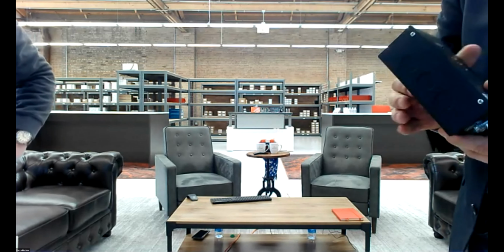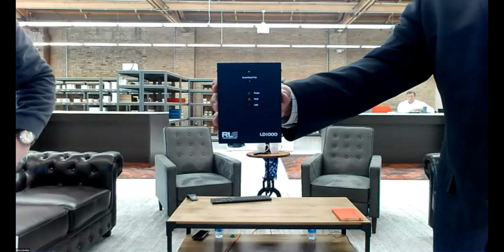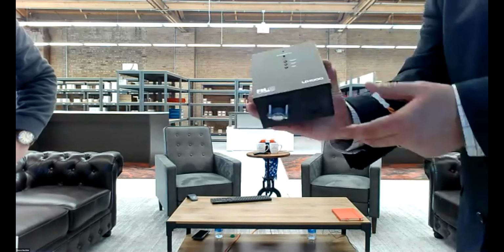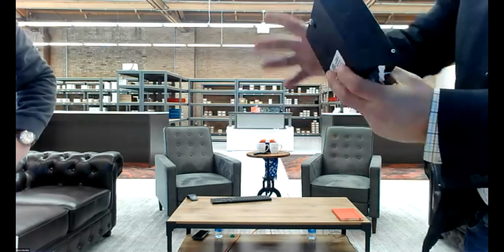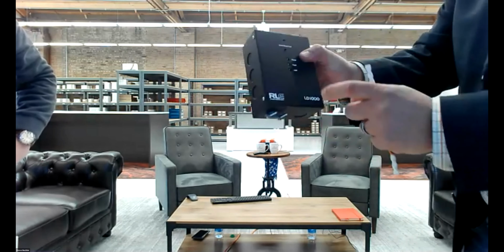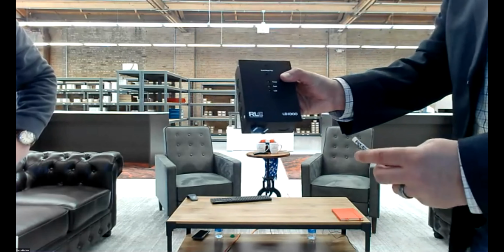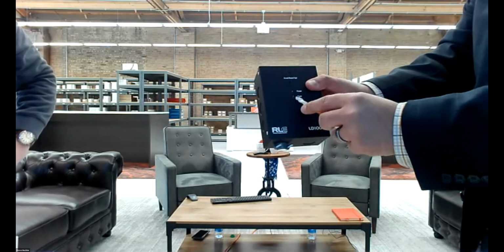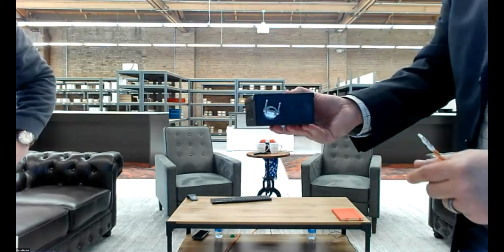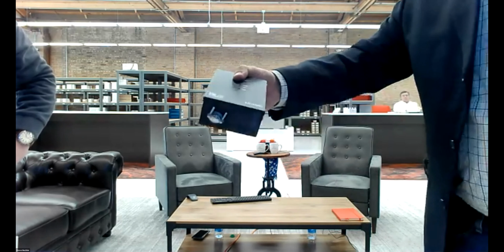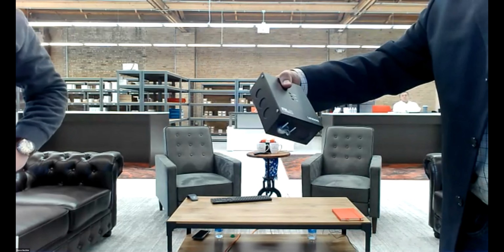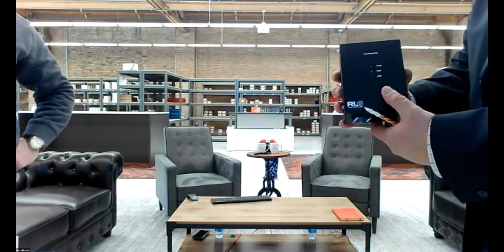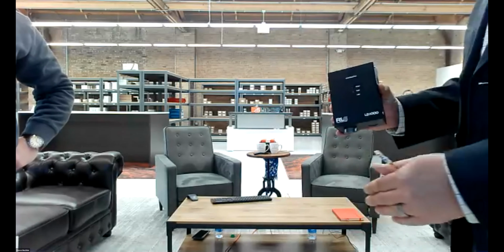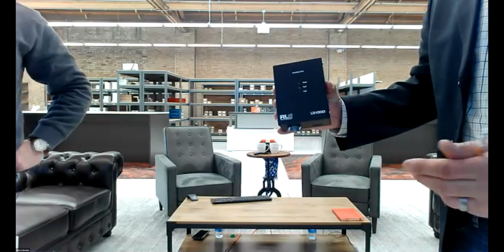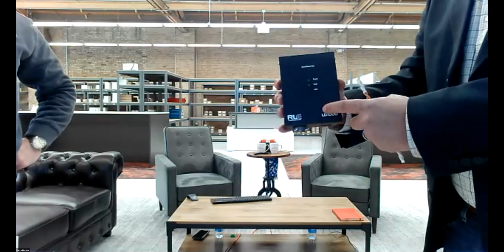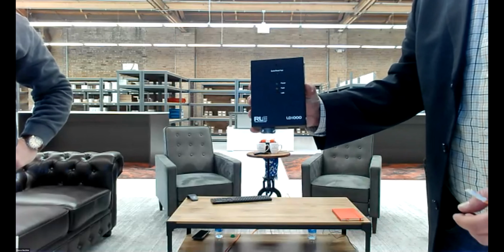Here's another controller, I like this guy a lot as well. This is our LD1000. As you can see, it's purpose built, ready to mount on a wall. It's a metal enclosure made in America. It's got indicators with power, leak fault, as well as a cable fault, a silencer here. It's got knockouts, I don't know if you can see the knockouts there. So, mechanical rooms, above ceilings, below floors, anywhere you want a visible indicator. And this will integrate as well with Modbus RTU and has a relay output.